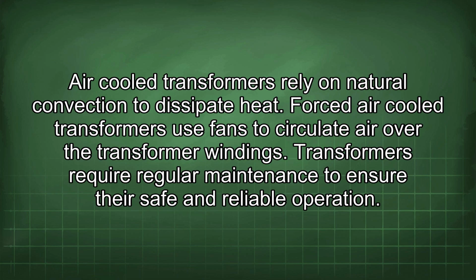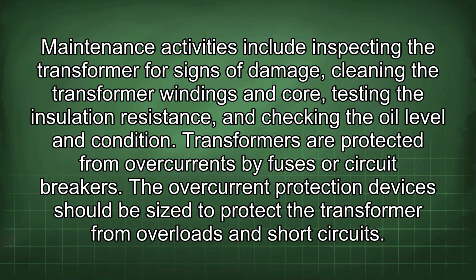Transformers require regular maintenance to ensure their safe and reliable operation. Maintenance activities include inspecting the transformer for signs of damage, cleaning the transformer windings and core, testing the insulation resistance, and checking the oil level and condition.